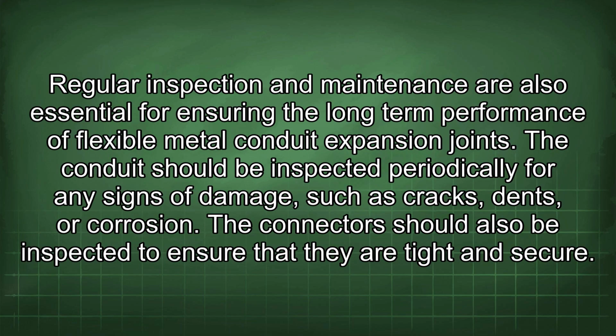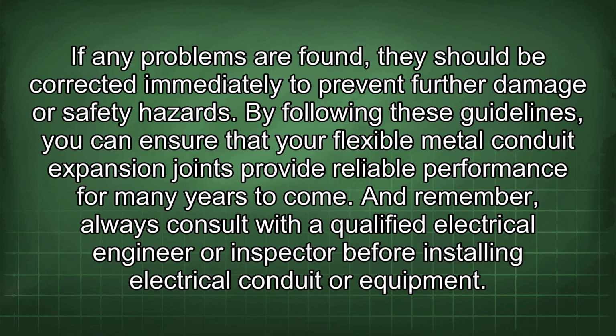Regular inspection and maintenance are also essential for ensuring the long-term performance of flexible metal conduit expansion joints. The conduit should be inspected periodically for any signs of damage, such as cracks, dents, or corrosion. The connectors should also be inspected to ensure that they are tight and secure. If any problems are found, they should be corrected immediately to prevent further damage or safety hazards.